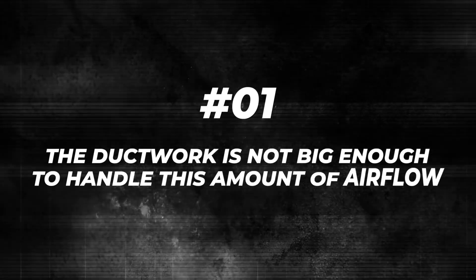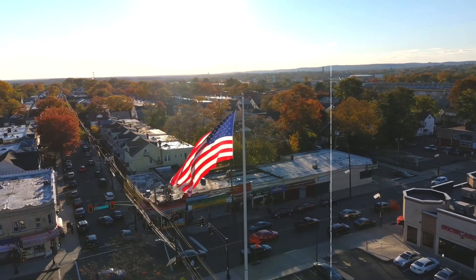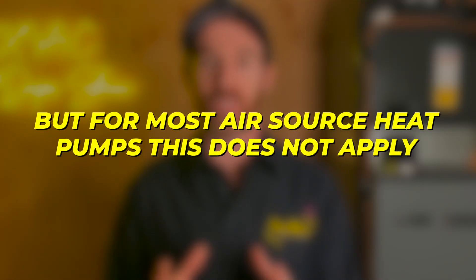But there are two problems with this. First, the ductwork is almost certainly not big enough to handle that amount of airflow. Second, even if it was big enough, now you have a 4-ton air conditioner on a house that only needs 2 tons of cooling, which means the system is going to be way oversized and short cycle in cooling season, especially if it's a single-stage system. For most air-source heat pumps, this issue does not apply.